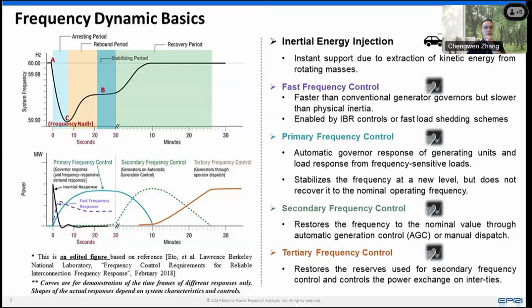Traditionally, we have the other three types of frequency response: primary, secondary, and tertiary frequency control. The primary frequency control stabilizes the system at a new level, and the secondary frequency control brings the system frequency back to the nominal frequency of 60 or 50 hertz. Then there's a longer term tertiary frequency control to optimize the power flow across the interties.